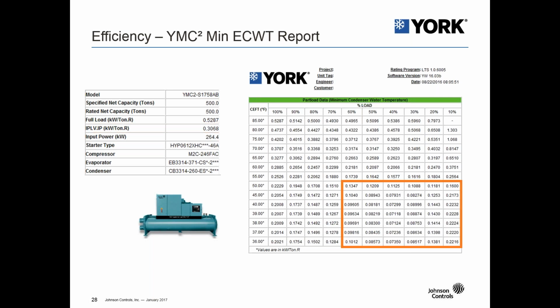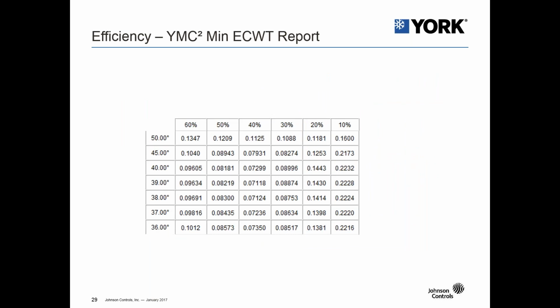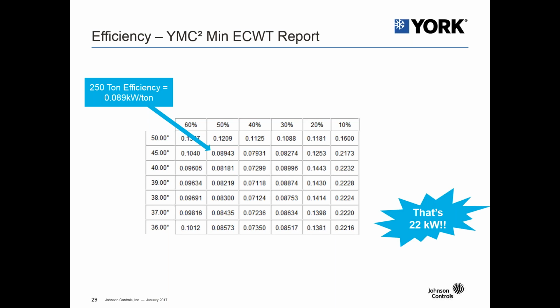So what we want to focus on is this area in the bottom right-hand corner. So we're looking at chiller loads at 60% and below, and we're looking at entering condenser water temperatures at 50 degrees and all the way down to 36 degrees. So if we look at 50% load or 250 tons for the chiller, utilizing 45 degrees entering condenser water temperature, it's at a 0.089 kW per ton. So below that 0.1 kW per ton that we talked about earlier. And while producing 50% of the chiller load, we're running that chiller at 22 kW.